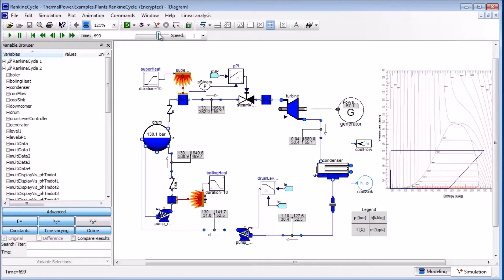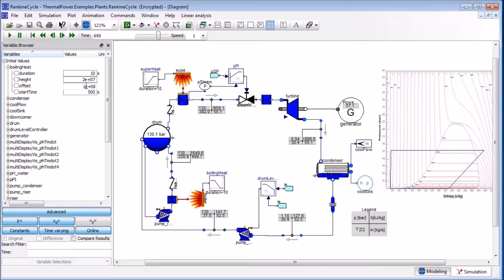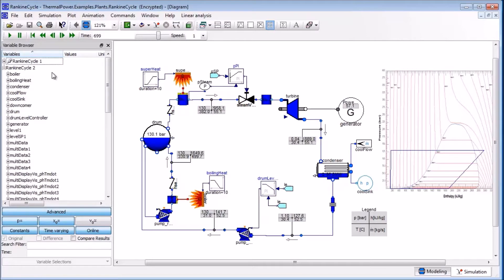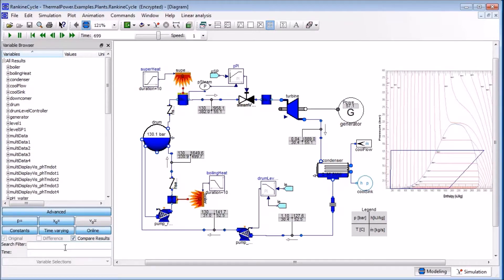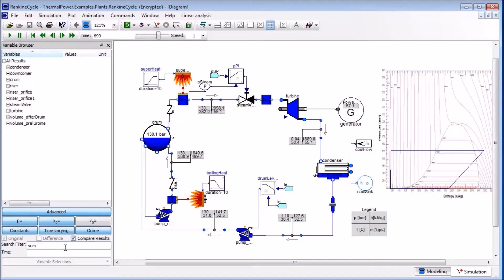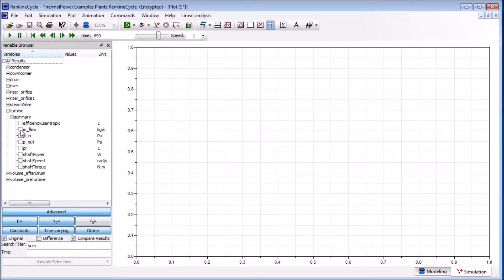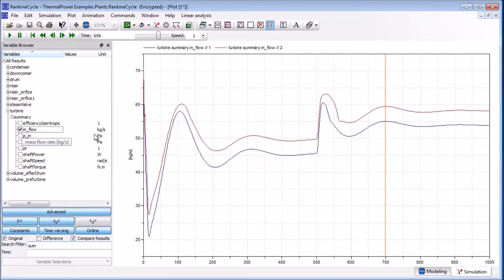It is also possible to quickly see how system parameters affect the result. Let's say we want to simulate the same system but with a slightly higher heat load. First we compile the model, then choose the boiling heat component, which specifies the amount of heat added to the system. We increase the offset by 10% and start a new simulation with the new slightly higher heat load value. After the simulation is finished, we enable the Compare Results checkbox and filter the result for summary variables to provide quick access to the most common and important variables. The Compare Results feature displays results from previous simulations in the same plot window — here we plot the steam mass flow rate through the turbine. Due to the additional heat, the steam mass flow through the turbine is higher compared to the previous simulation.